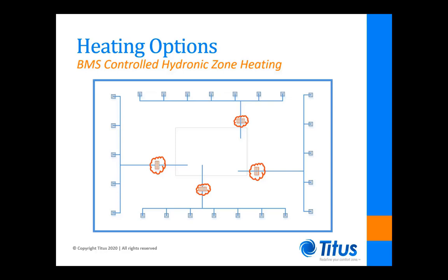The coils can be controlled by the BMS, which when integrated into a VAV diffuser network, can read the room temperatures from the stats on each of the master diffusers. A voting control strategy can be used to decide which and when each heater is energized. This heating strategy is best suited to larger projects with a budget for a building automation system.